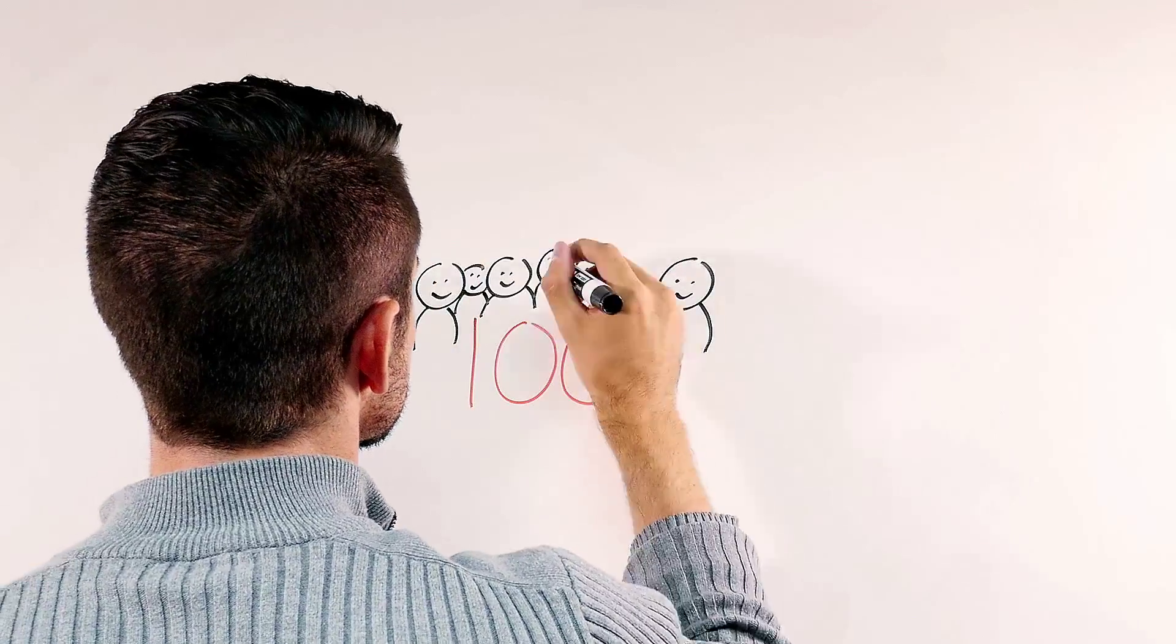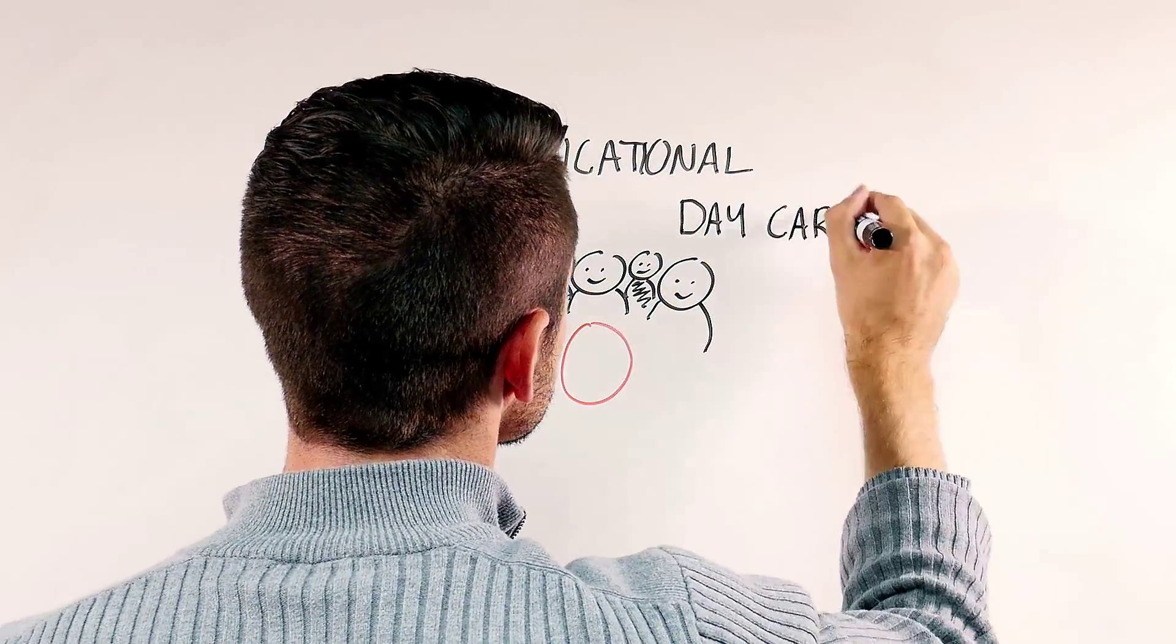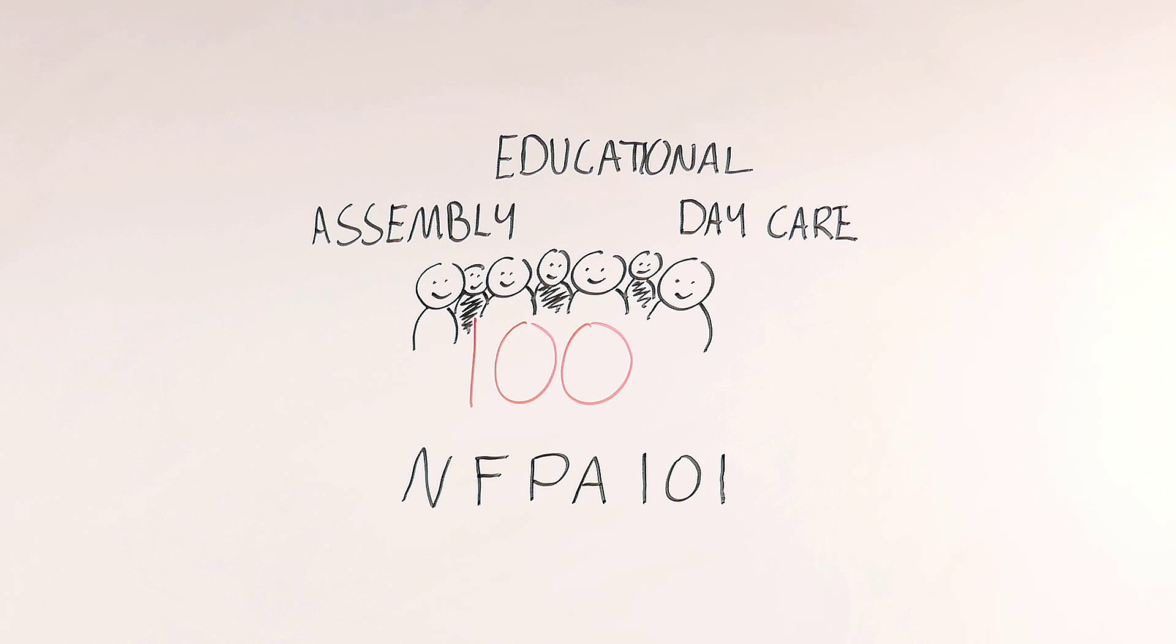NFPA 101 requires panic hardware for doors serving assembly, educational, and daycare occupancies with an occupant load of 100 people or more, and for areas with high hazard contents that have an occupant load of more than five people.